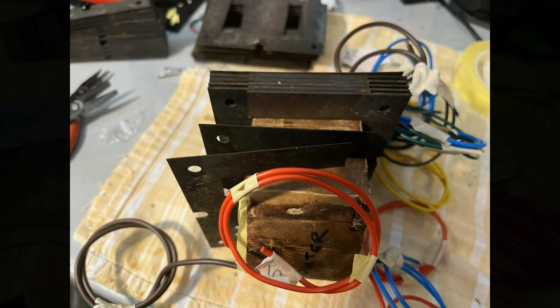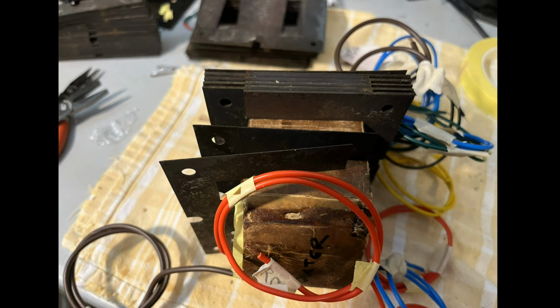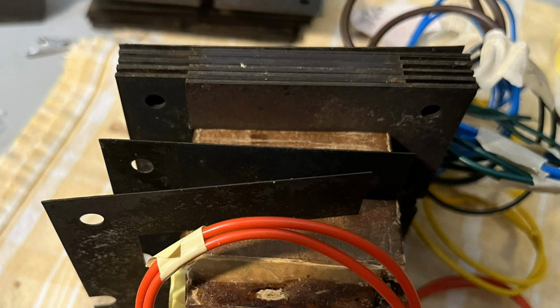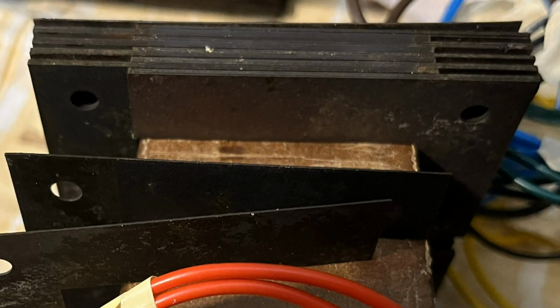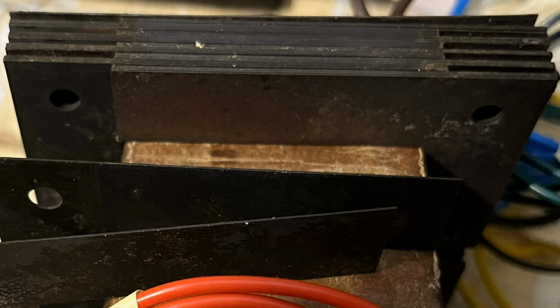In this image, I'm installing the E-laminates in opposing directions. Each laminate is actually a small bundle of 3 leaves, which is how the transformer was originally constructed. Note that the gaps on alternating sides between each E-laminate is a space for the I-laminates, which are installed after all E's are in place.